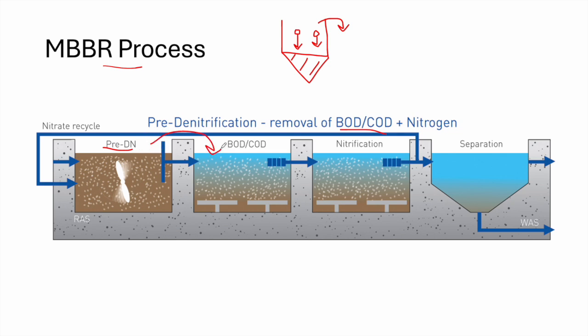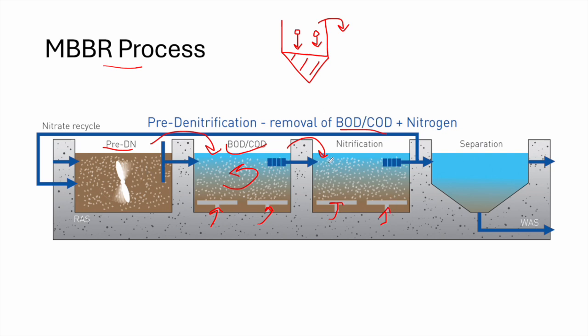The small dots represent the MBBR media moving within this reactor — this is the pre-denitrification stage. Then the wastewater goes through aerobic conditions by diffusing air through diffusers, creating aerobic conditions and media motion. Through this stage, BOD and COD are highly reduced, followed by the nitrification stage also under aerobic conditions.